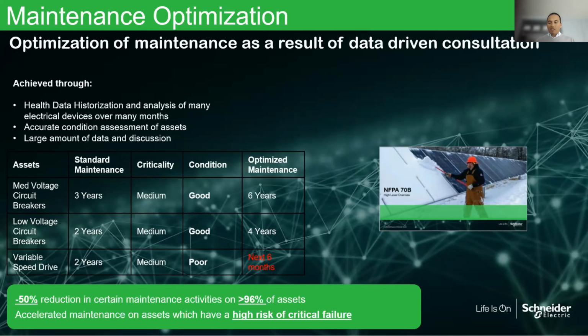We're able to say, if these conditions persist and we continue to operate the breaker this way, we could extend maintenance on medium voltage breakers from 3 years to 6 years, and on low voltage breakers from 2 years to 4 years—continuing regular level 1 inspections and monitoring to confirm conditions haven't changed.